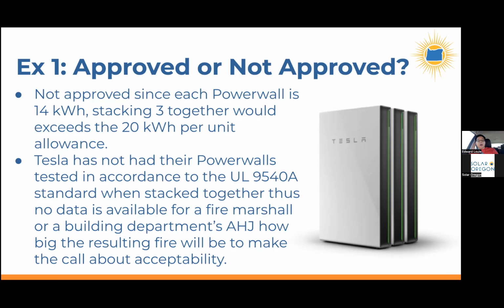So currently, if a jurisdiction actually follows these rules, then the fire marshal or building department's authority having jurisdiction does not have any test data to read and understand, well, how big of a boom, how big of a fire, how much smoke will get generated if 3 of these Powerwalls were stacked together and one of them goes into thermal runaway. And so since there's no data, being a really risk-averse society, you might not get an AHJ or a fire marshal to just blindly trust that the test results from 1 will then translate to having 3 stacked together.